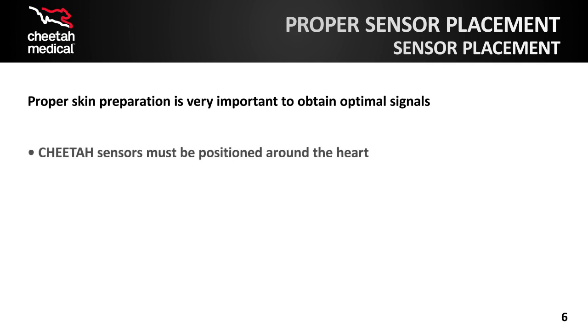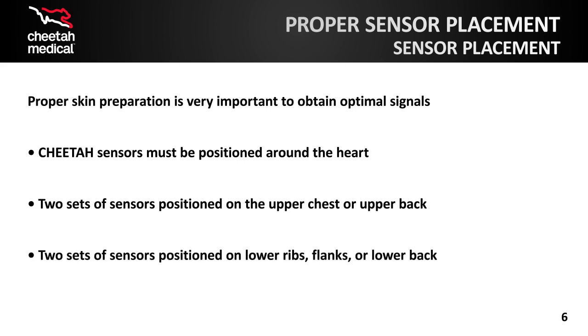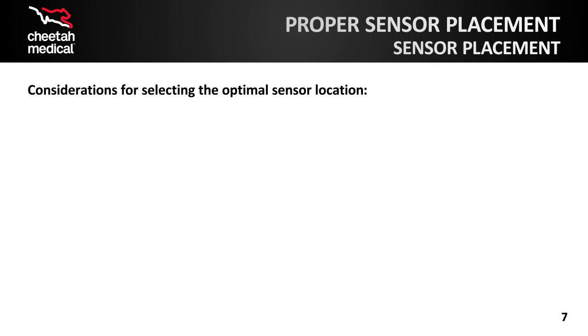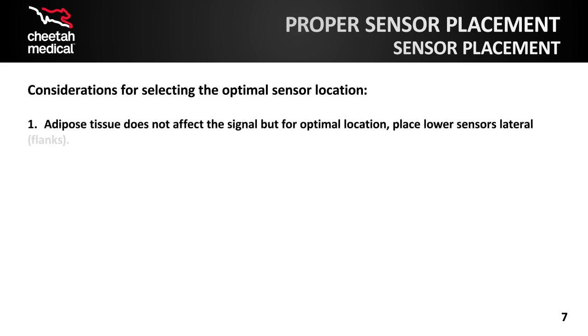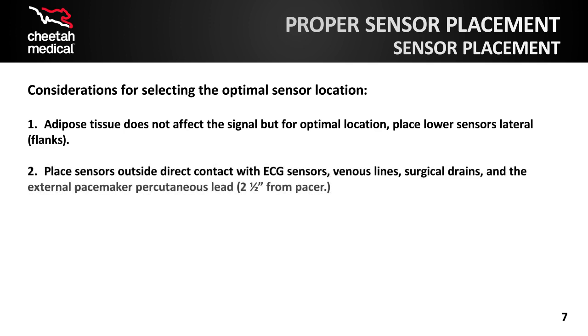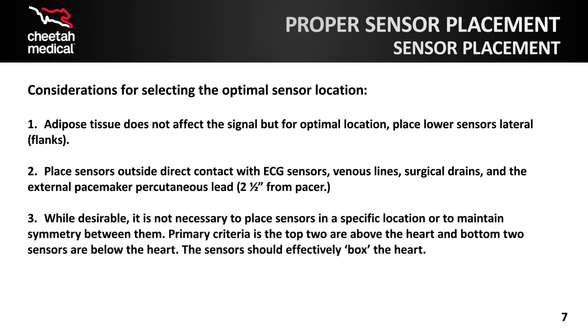Cheetah sensors must be positioned around the heart. 2 sets of sensors positioned on the upper chest or upper back. 2 sets of sensors positioned on the lower ribs, flanks, or lower back. In selecting the optimal location for the sensors, consider the following. 1. For optimal signal quality, lateral location is preferred for the lower pair, especially in obese individuals. 2. Find a spot that is outside direct contact with ECG stickers, venous lines, surgical drains, and the external pacemaker percutaneous lead. 3. It is not necessary to place sensors in a precise location or to maintain symmetry between them.